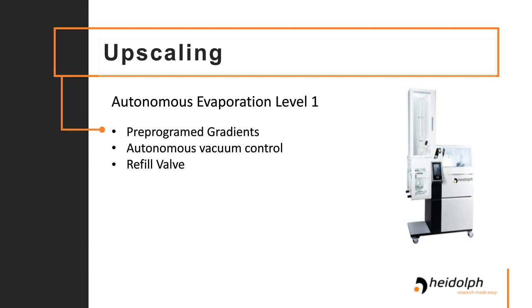That autonomous vacuum control can be set, so again, it can be efficiently evaporated without you having to be there. It'll work with both your industrial size and your benchtop units. And making use of the refill valve means you're not removing that evaporation flask as often. That way you can save time from having to pull down the vacuum again and the time it takes to remove the evaporating flask, and you can really optimize your process to get as much out of it as possible.